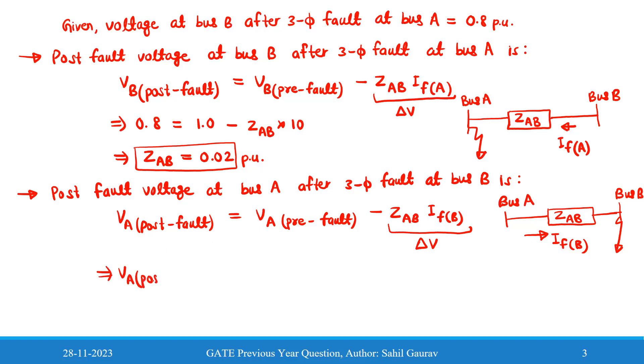V_A(post-fault), voltage at bus A. Pre-fault voltage at bus A is 1.0 per unit, Z_AB we have calculated in the previous expression, and I_fB is 8 per unit. So we will get 1.0 minus 0.16, it will be equal to 0.84 per unit. This is the final answer.